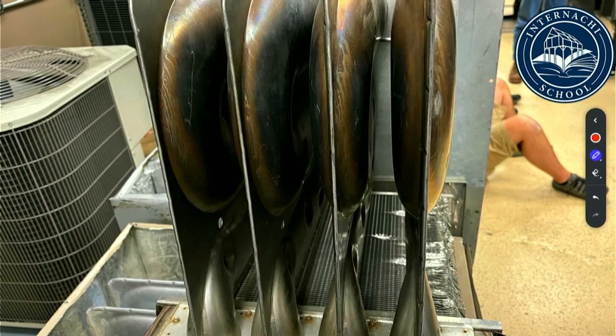Same thing, rear end. On this one we've got our primary and our secondary. Primary comes in the top, a lot of heat on this one. This thing is actually pretty black up in here, but I don't see too many other issues. There's a possibility that could be a crack, and that's always a problem with pictures, you can't see it from a different angle. I know this is a scratch, so that's not it. It just had some extra heat on it.